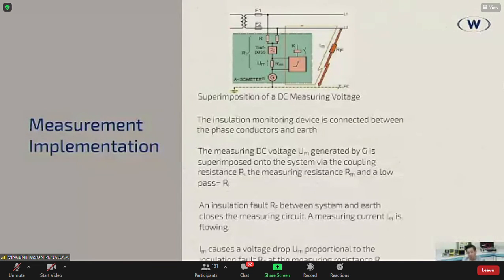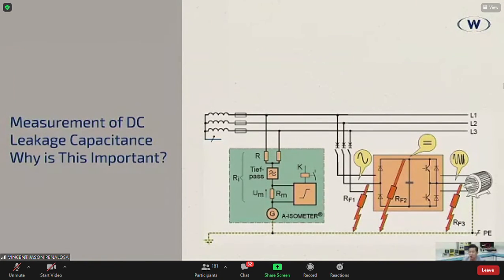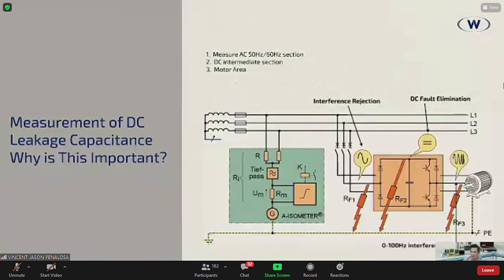Now, kanina we were talking about measurement of leakage capacitance, why this is important. This is the reason why, because now we already have either nonlinear loads, we have frequency variation, and so on and so forth, right? And we will have DC components. We will have pure AC sinusoidal waves, and we will have a combination of both. And sometimes a lot of those superimposed DC voltages that are introduced into the AC circuit give us a little bit of problem, no? So insulation monitoring devices look into the measurement of the 50 or 60 hertz section. They look into the DC intermediate section, and of course the motor area or the load area. There you go. So you have interference rejection, you have DC fault elimination to clean up its own measurement, right?